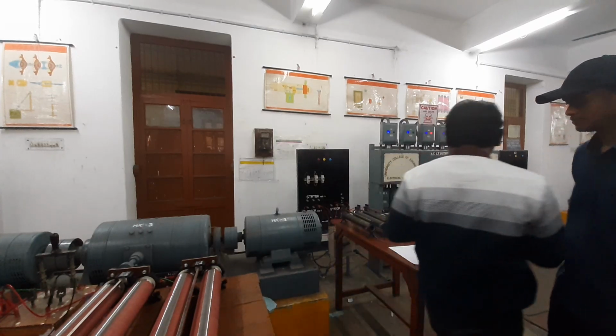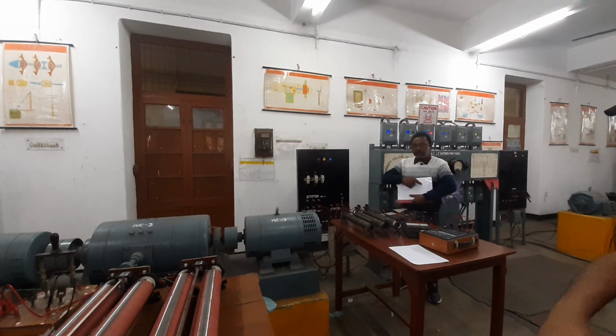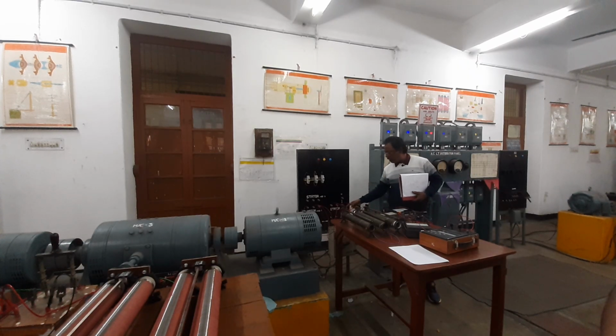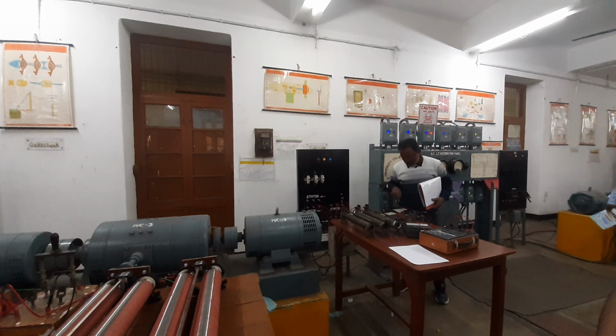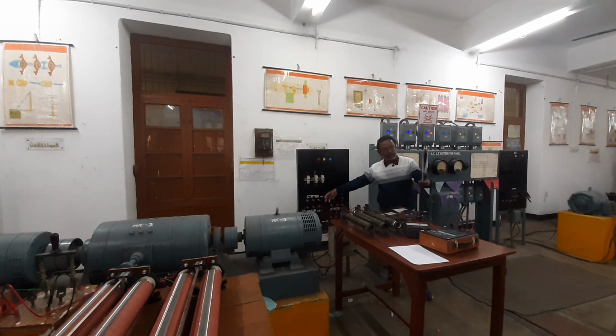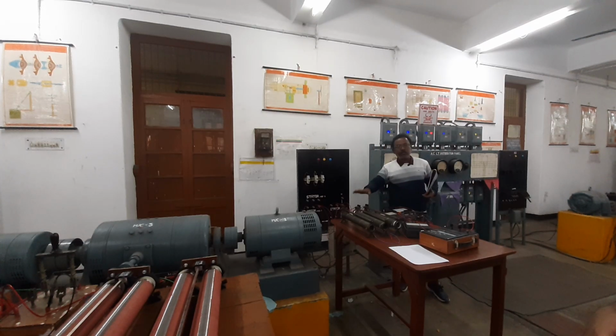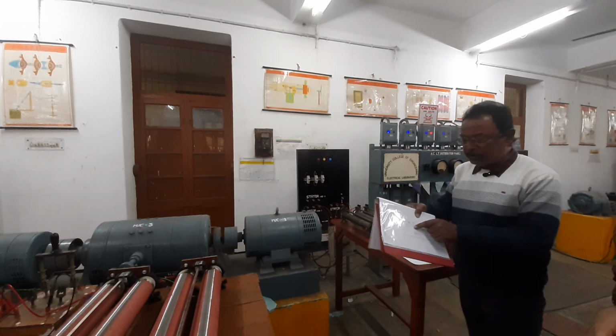For that purpose, you see, this is the motor part, these are the connections. L1, L2, L3 are the supply terminals. The ammeter is connected, and the wattmeter. This one is the wattmeter. L1 and L2 is the main supply, to be connected to the starter of the motor. And as the rotor is a slip-ring type, this motor should have external resistance. Three external resistances in a balanced way should be in star form, like this.